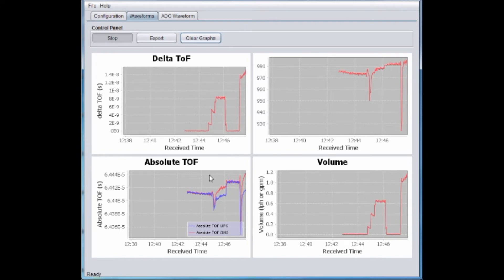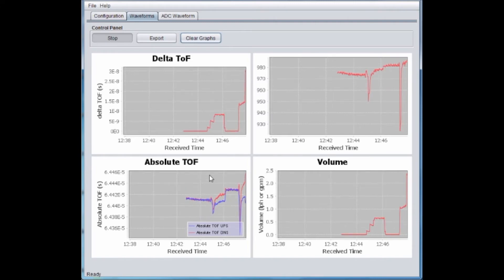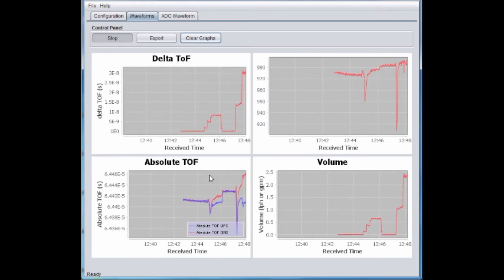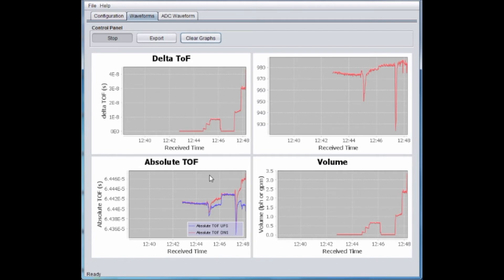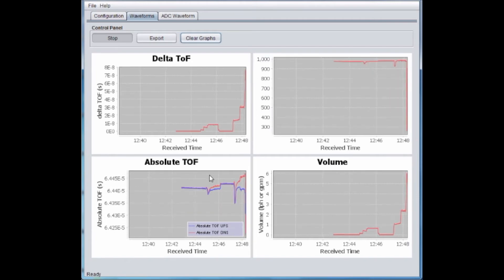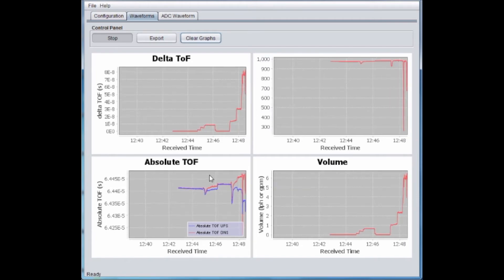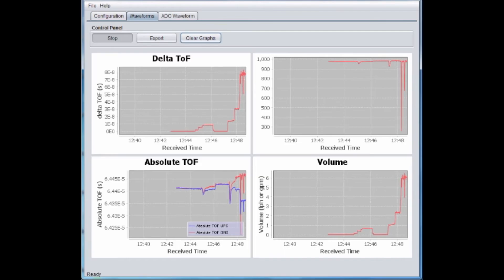We will also need calibration at two or three points on the flow rate curve, which depends on the characteristics of the flow tube. This shows the measured flow rate against the flow rate displayed by the reference meter, demonstrating the high accuracy of the solution at all flow rates, including the lowest flow rate of around 0.1 liter per hour.